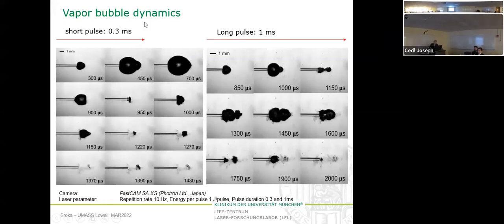But all this is a little bit dependent on the vapor bubble dynamics and on the duration of the vapor bubble. Here, as you can see, short pulse, this is 300 microseconds, and this is a long pulse, this is 1000 microseconds. And you can clearly see here, okay, this is the maximum which can be reached, and then it collapses in front of the stone. In the case of the long pulses, you can see there is first this vaporization, then the energy of the laser is transmitted through this first bubble, and you get a second bubble. When we follow it, we can punch through to the second bubble as well. So we have an ellipsoid or longitudinal bubble, not that odd shape like here, and then it collapses again.